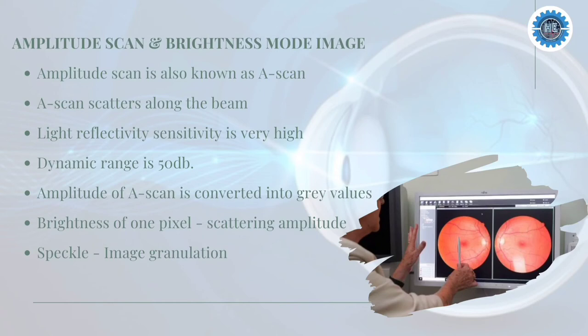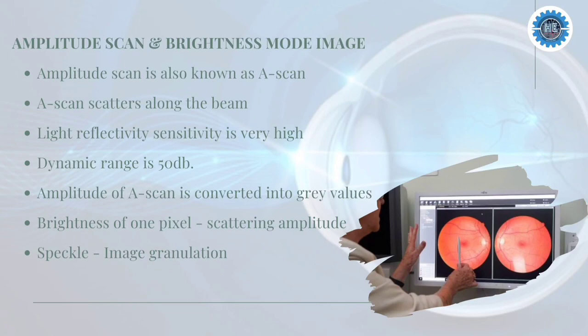As in ultrasound, an image is formed by placing a row of A-scans next to each other. In Optical Coherence Tomography, this is usually done by scanning the beam transversely with scanning mirrors and optics. The amplitude of A-scans is converted into gray values, where the brightness of one pixel is related to the scattering amplitude at that position. Due to the interferometric measurement, there is a phenomenon called speckle — a granulation of the image — since backscattering in the sample usually does not create a perfect wavefront, resulting in different scatterers in the volume. There is a mixture of constructive and destructive interference resulting in one pixel value, and in some cases speckles are not just noise but may contain information in their statistics.